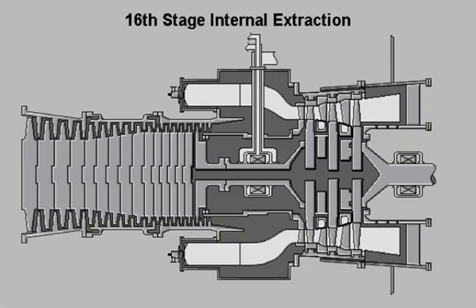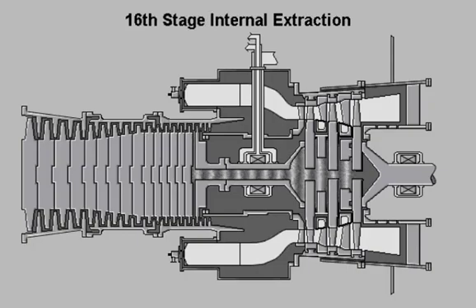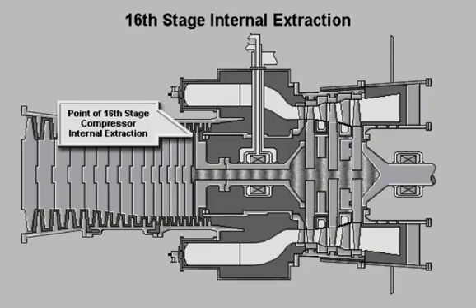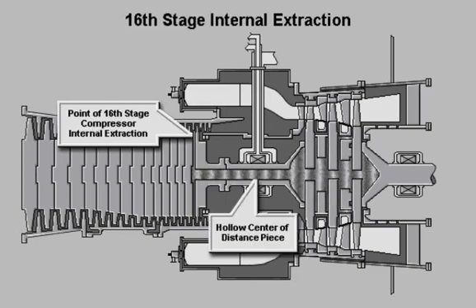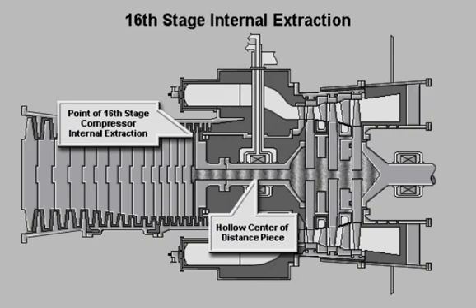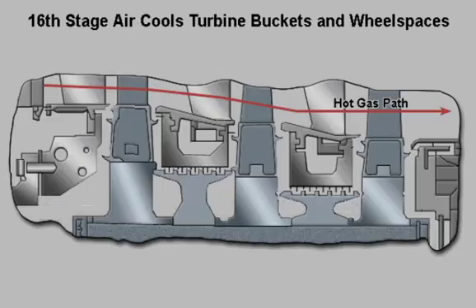During normal operation of the gas turbine, a portion of the compressor discharge air is internally extracted through the wheel space that exists between the 16th and 17th compressor stages. This air passes through the hollow centers of the distance piece and the turbine rotor.